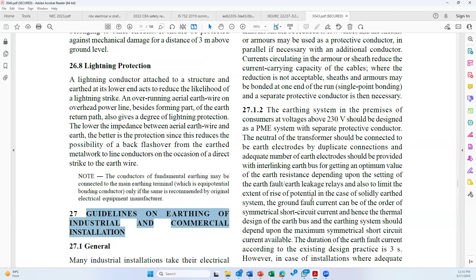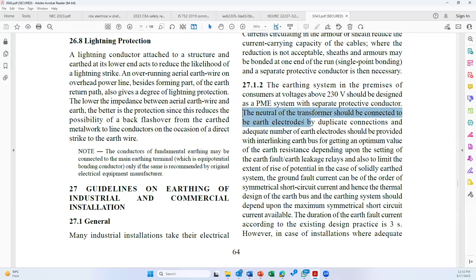What you can do is go to clause number 27 of the existing IS 3043. It explains what you should do. For example, I'm taking clause 27, the guideline on earthing of industrial and commercial installations. We are talking about a steel industry. I'm reading 27.1.2: the earthing system in the premises of customers of voltage above 230 volt should be designed as a PME system with separate protective conductor, meaning you have to have a TN-S system. The neutral of the transformer should be connected to the earth electrode by duplicate connection.